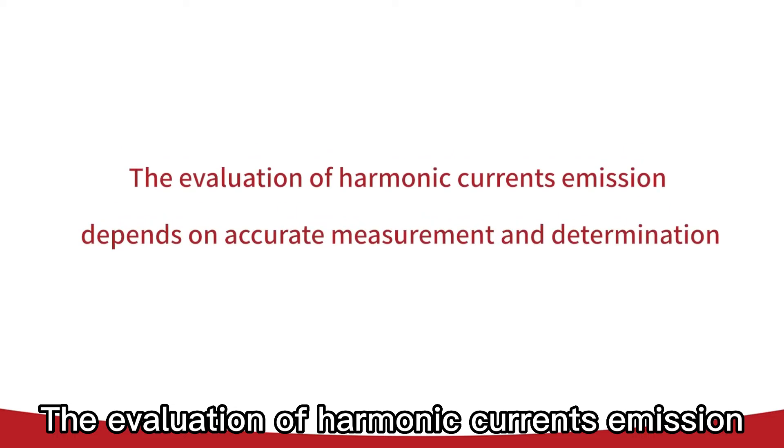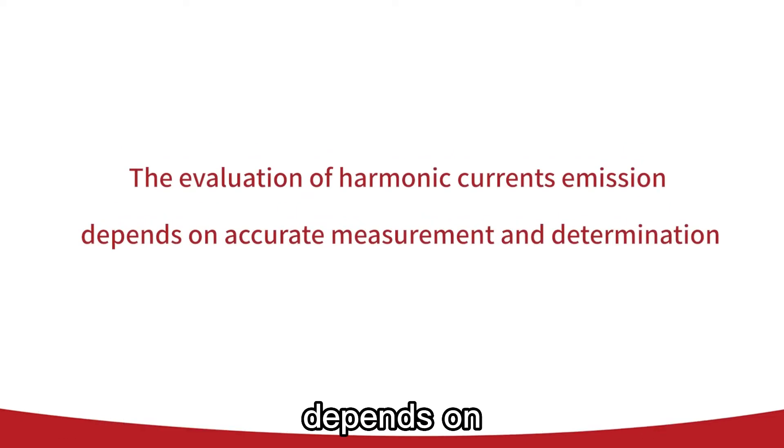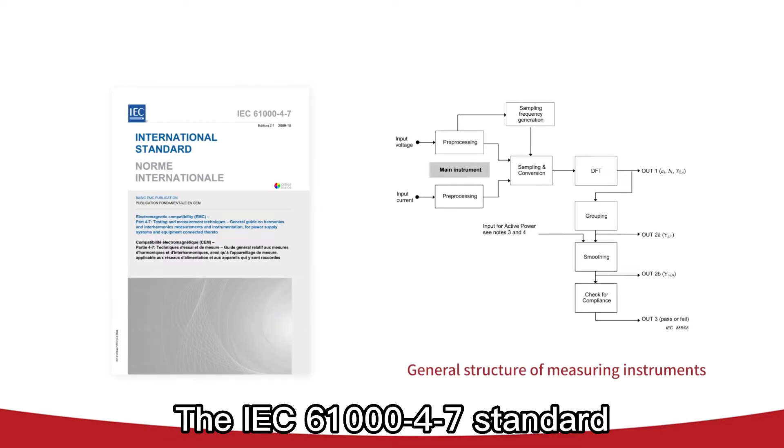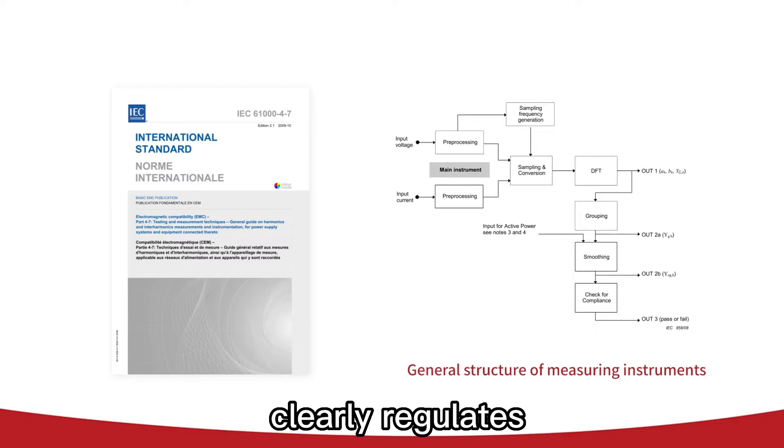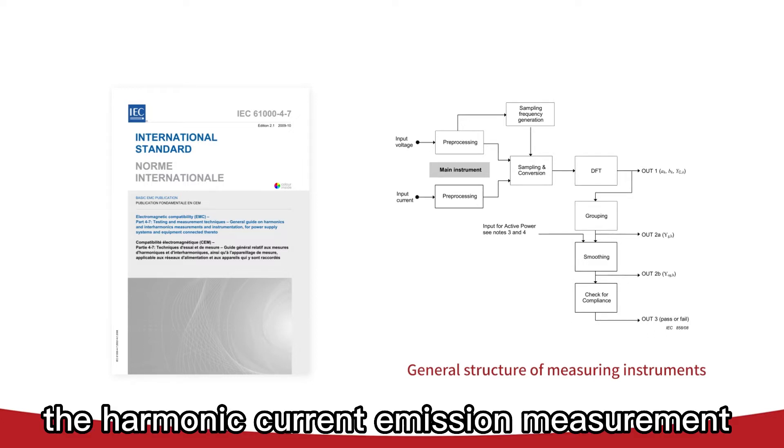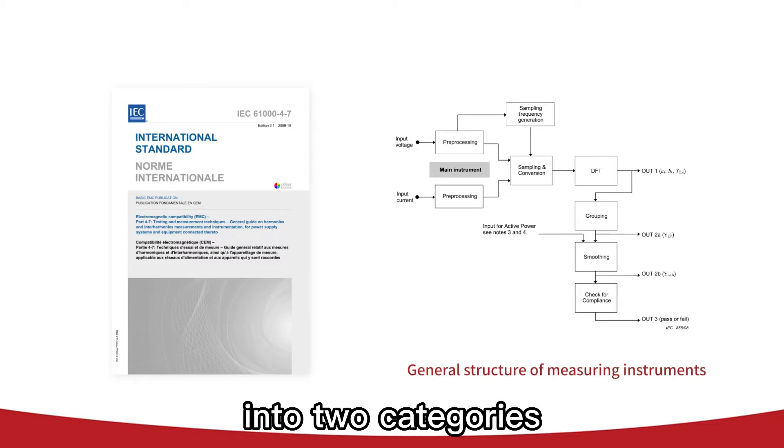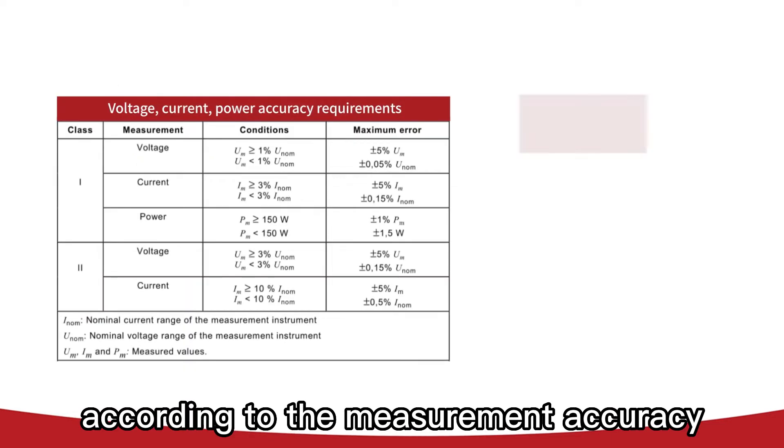The evaluation of harmonic current emission depends on accurate measurements and determination. The IEC 61000-4-7 standard clearly regulates the harmonic current emission measurement methods and divides the instruments into two categories according to the measurement accuracy.